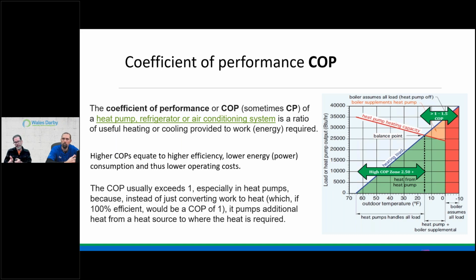It's achievable. Be understanding of the fine print. When you look at any of this stuff, I'm holding up, any of these manufacturers, they're all playing nice with maybe AHRI testing. So you have to understand what the parameters were at the time of their testing to show you these high, amazing numbers to buy in. And then we have to apply it to reality. So where are the real deep dive charts? I want to know what the BTU output is when it's 0 degrees outside. The chart you're showing me is at 46 degrees outside. That's not reality. So again, you're going to have to be a little deeper diver into the information trail.